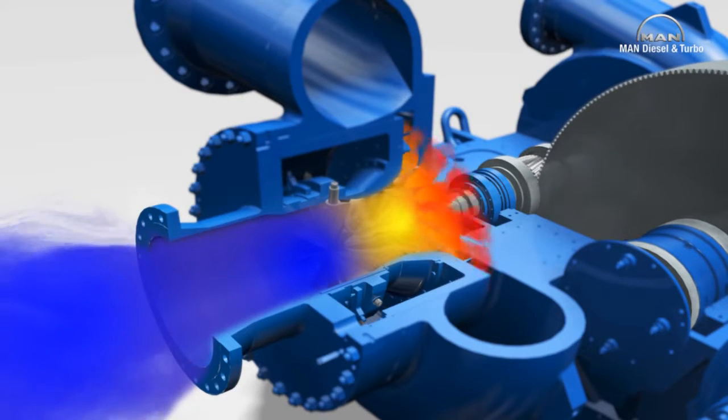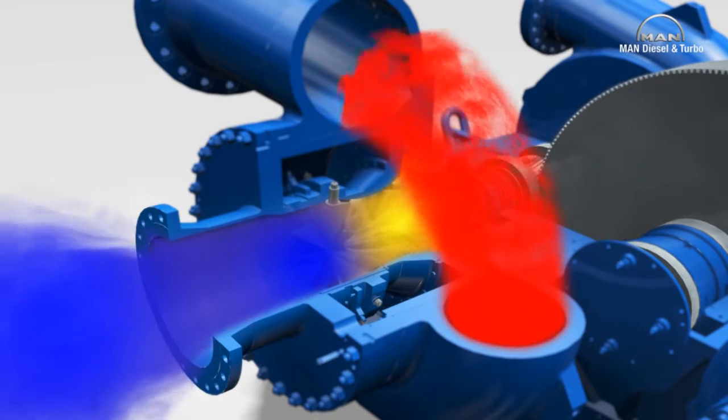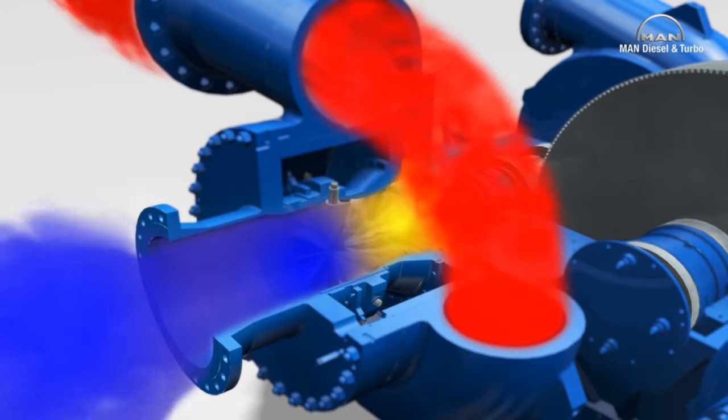Centrifugal force works here in the same way as with a roundabout, and accelerates the gas radially in the blade channels, that is to say from inside to outside. This provides the gas with kinetic energy, which is transformed into pressure energy in the impeller and diffuser. The volute then collects the gas.